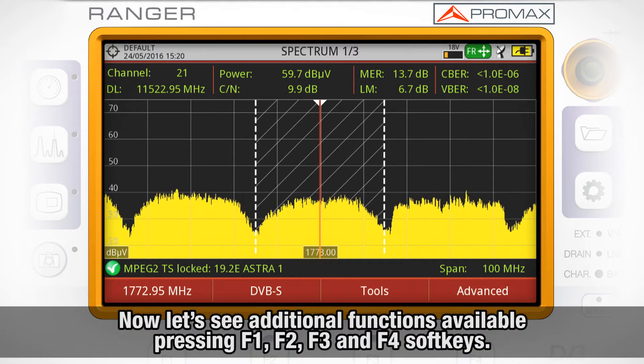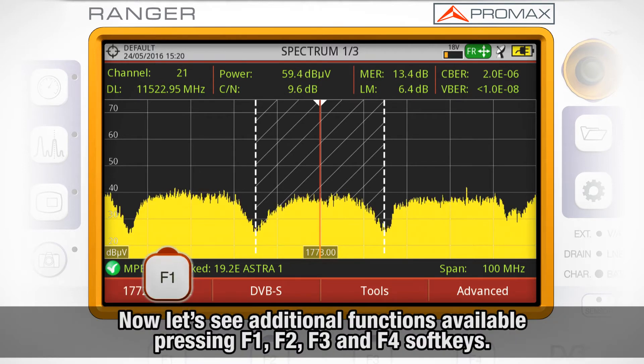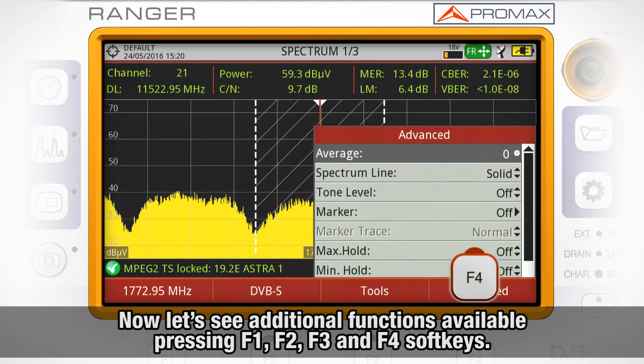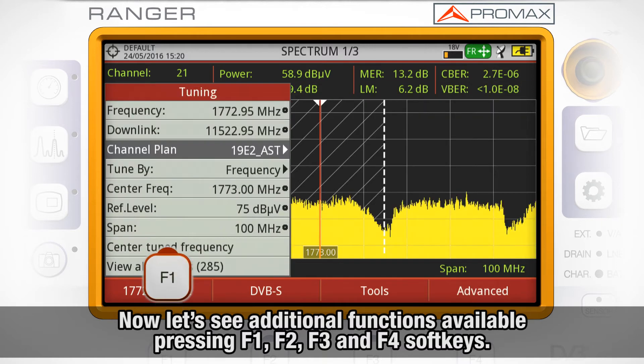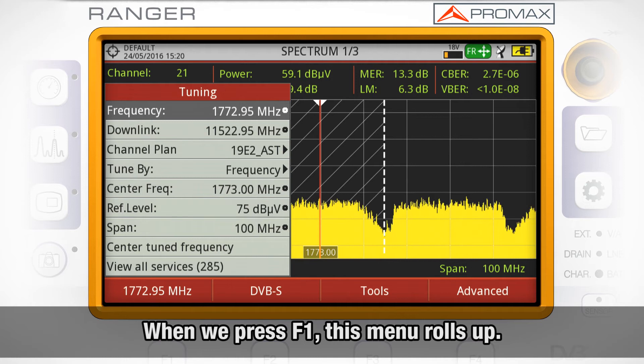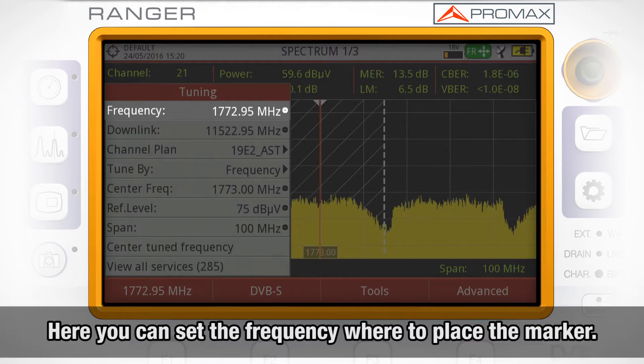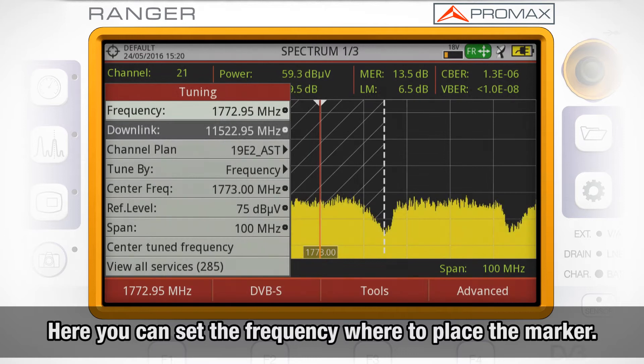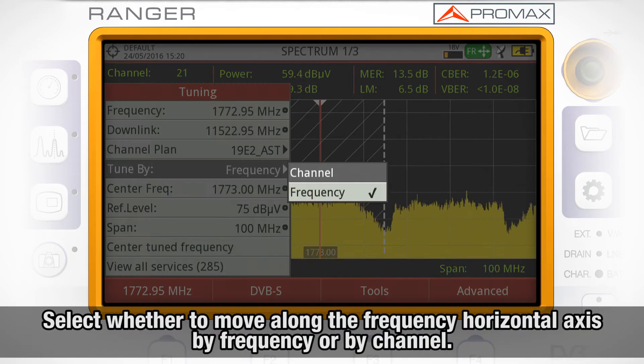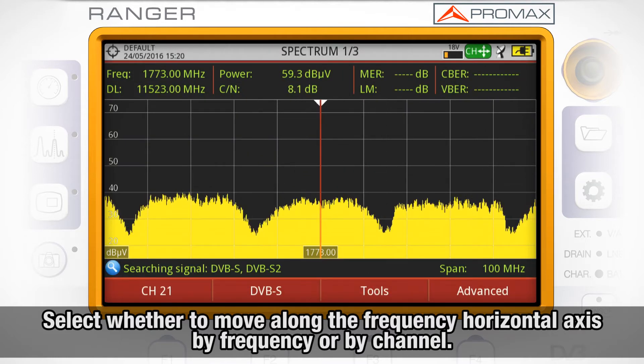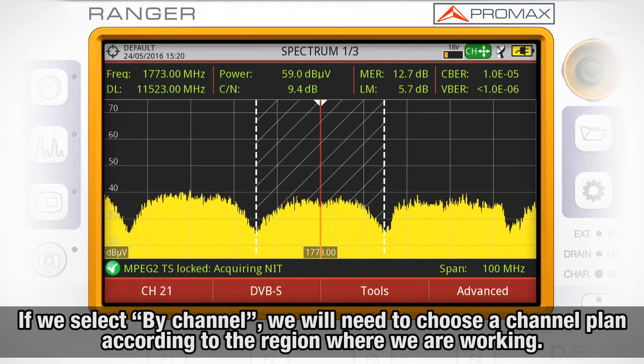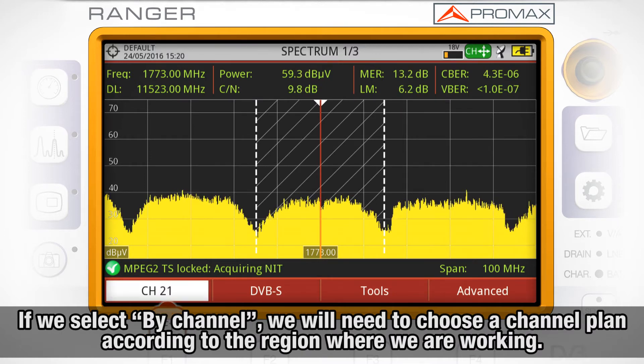Let's see some additional functions that we can access by pressing the soft keys below the screen: F1, F2, F3, and F4. When we press F1, this menu rolls up. Here you can set the frequency value where we want to place the marker. You can select whether you want to move along the frequency horizontal axis by frequency or by channel.